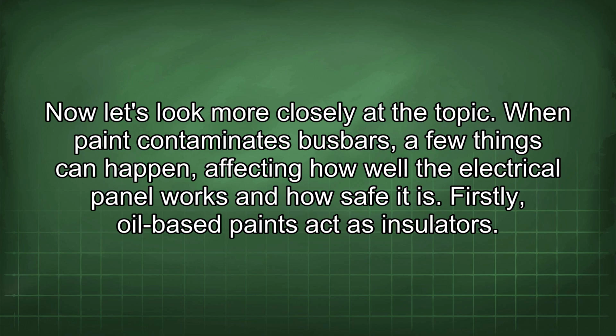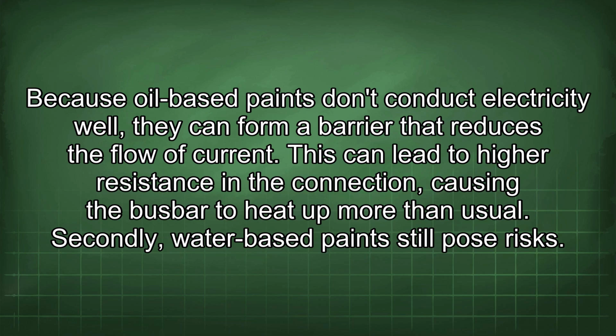When paint contaminates busbars, a few things can happen, affecting how well the electrical panel works and how safe it is. Firstly, oil-based paints act as insulators. Because oil-based paints don't conduct electricity well, they can form a barrier that reduces the flow of current. This can lead to higher resistance in the connection, causing the busbar to heat up more than usual.